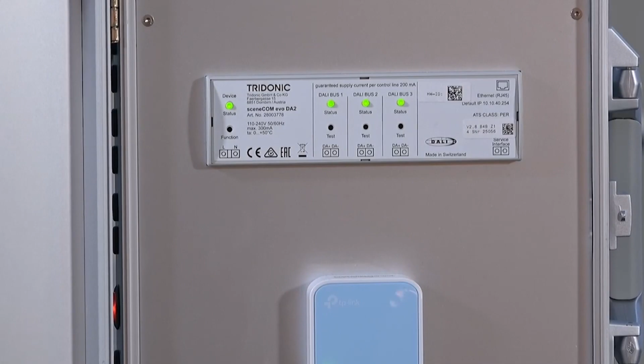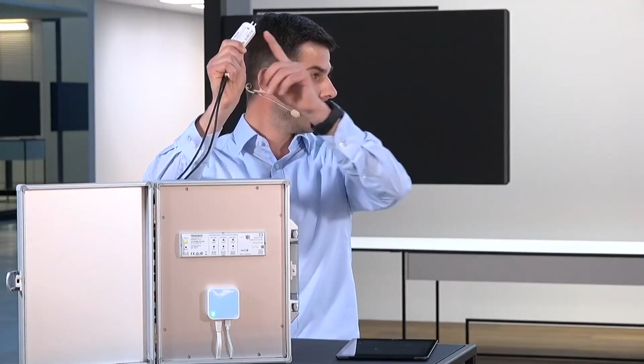It has 3 DALI lines, and it searches for unaddressed luminaires. When we talk about the process now, it really goes through the DALI line, the connected line, and searches through this DALI gateway to see if there is any unaddressed luminaire. That means for my emergency wireless luminaires that I have now built up with the wireless node inside, they will be registered as luminaires already here in the SceneCom.